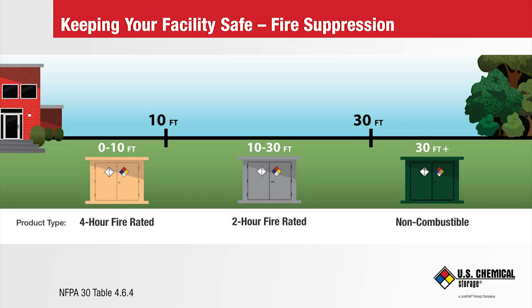Codes written by NFPA, OSHA and the International Fire Code all have very similar but not exactly alike setback distances. For example, most codes require the building to be 4-hour fire rated when within about 10 feet of another building. But adding a sprinkler fire suppression system will reduce the fire rating to 2 hours. At the other extreme, a hazmat building more than 30 feet from buildings, roads, and property lines does not have to be fire rated or protected by a fire suppression system.